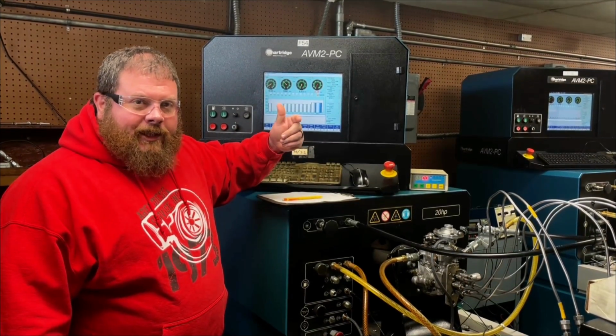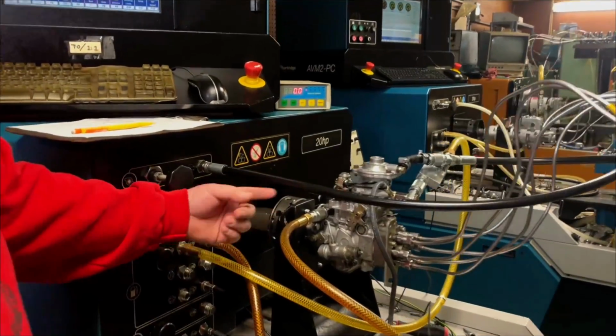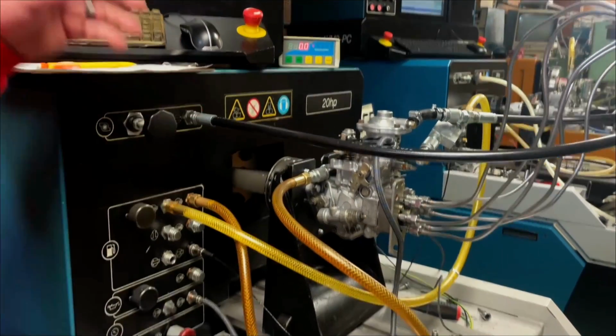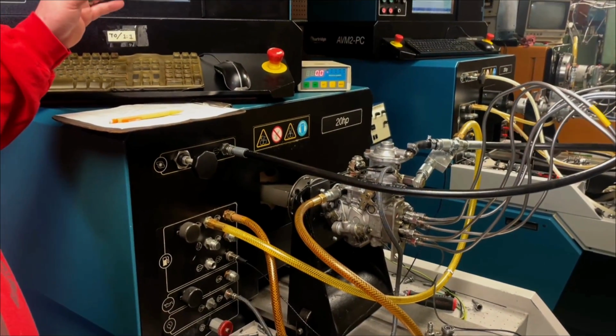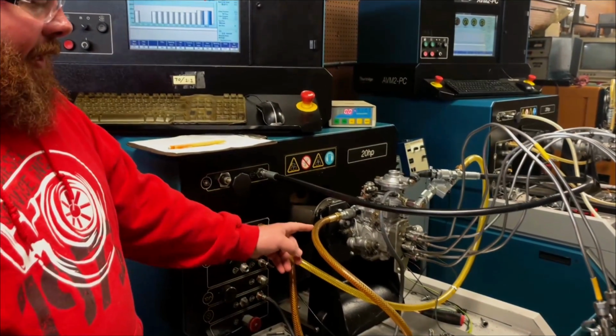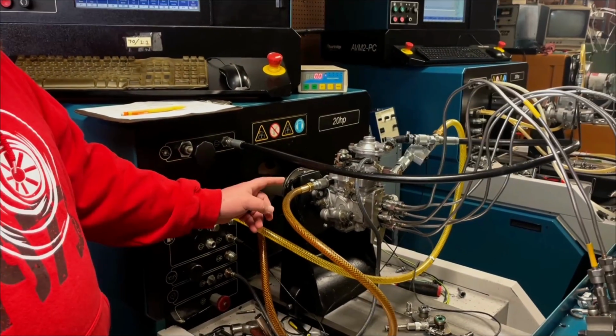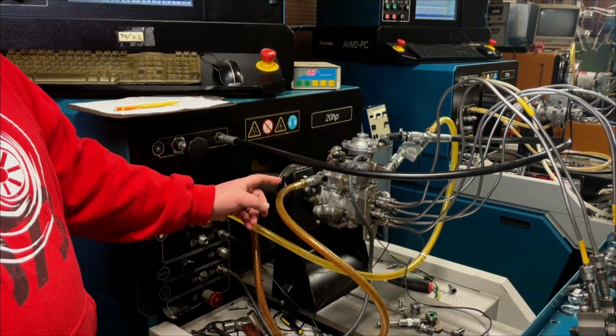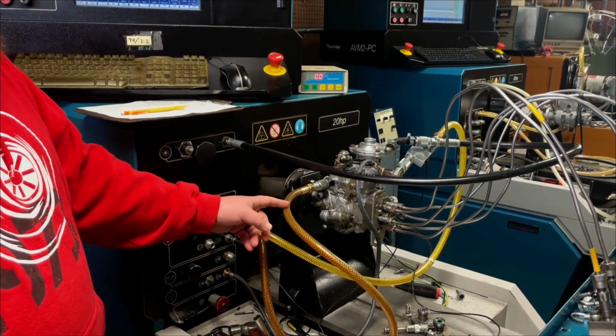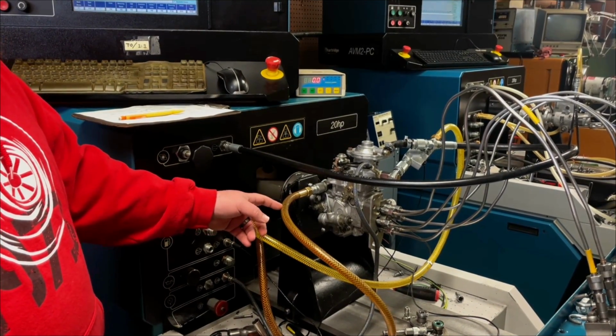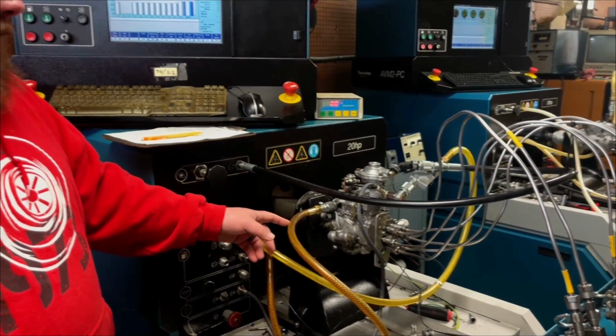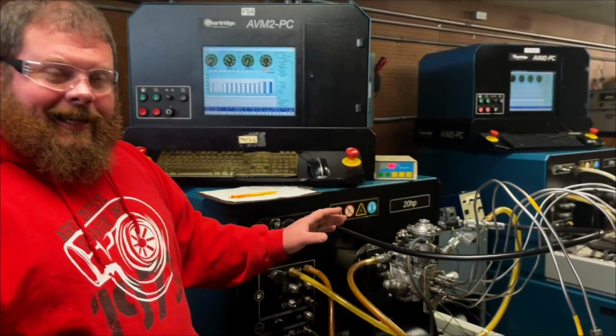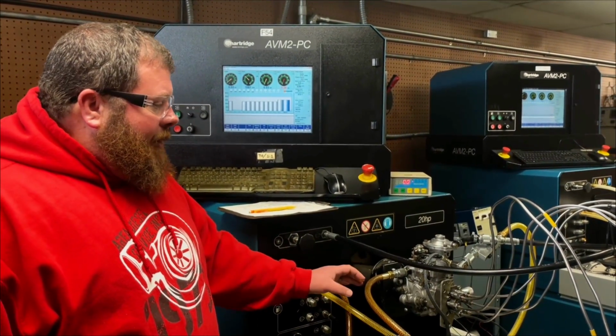There's a motor in here that's going to turn the pump. We dictate to the stand what RPMs to turn it at. We're feeding it calibration fluid here. We don't use diesel fuel because diesel isn't always consistent, so we feed it a scientifically tested calibration fluid, ensuring a static and consistent fluid to the pump.